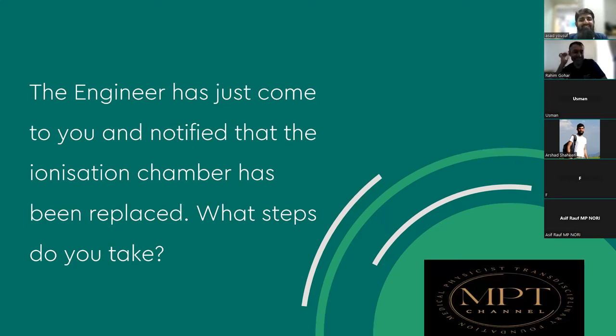Okay, so beam output should be verified, beam profile, flatness, symmetry, and beam quality, of course. And also the safety features should be checked, whether MU1 and MU2 are working properly, and other recommendations from the engineers and vendors, because they provide the booklet.